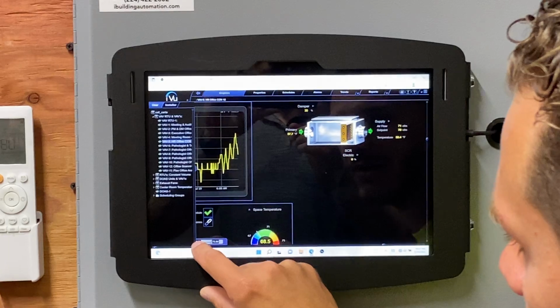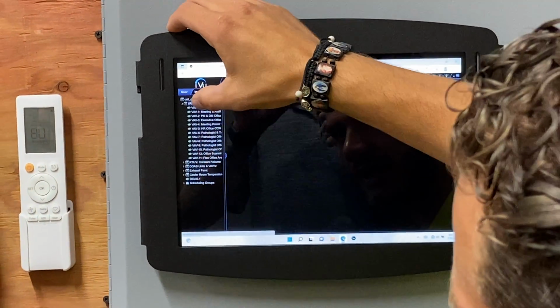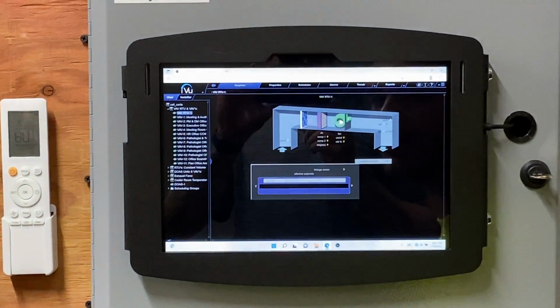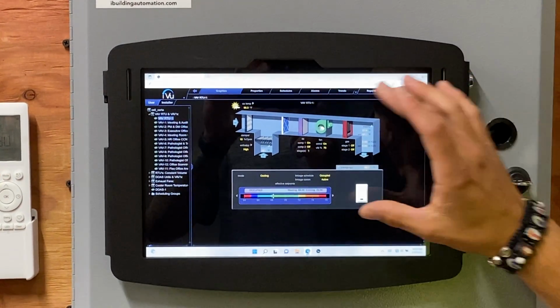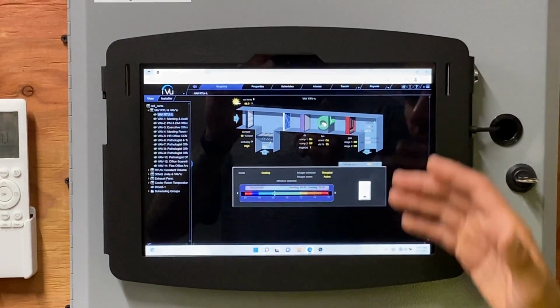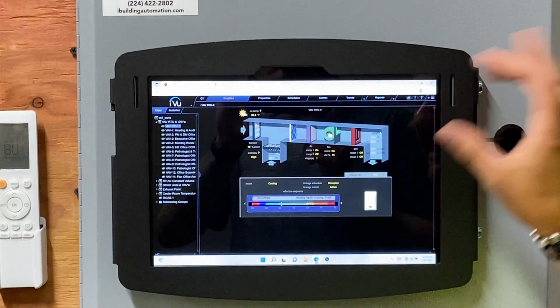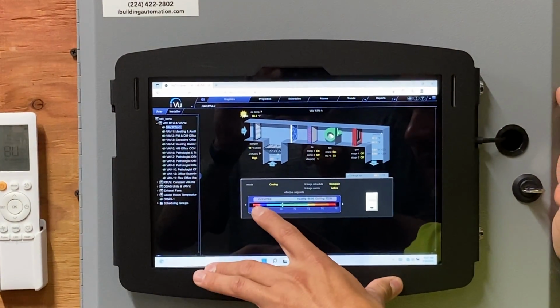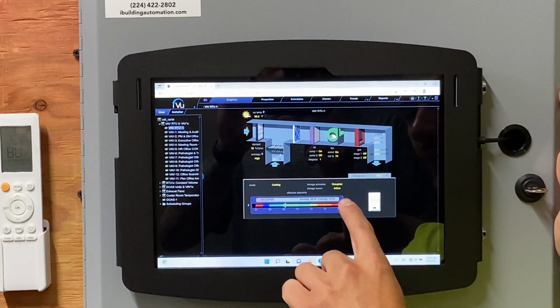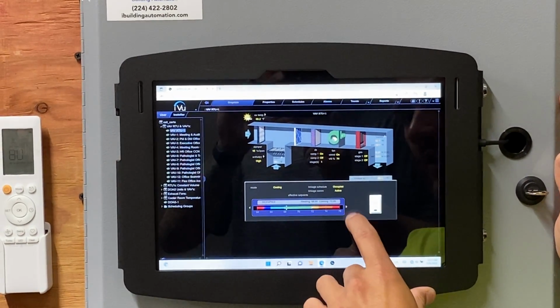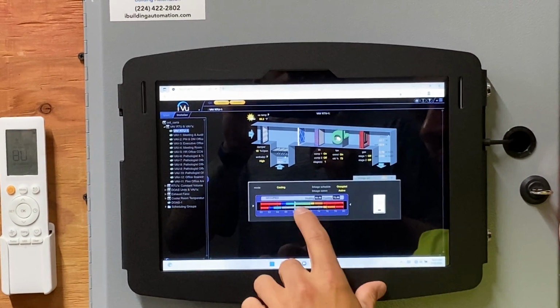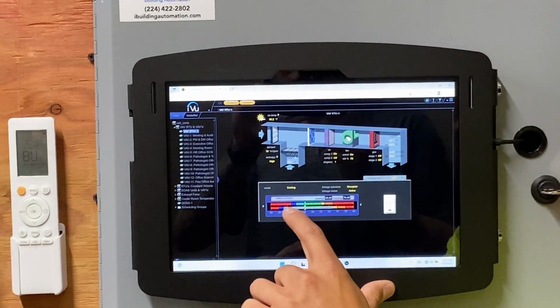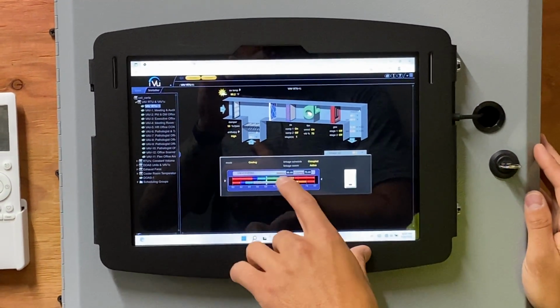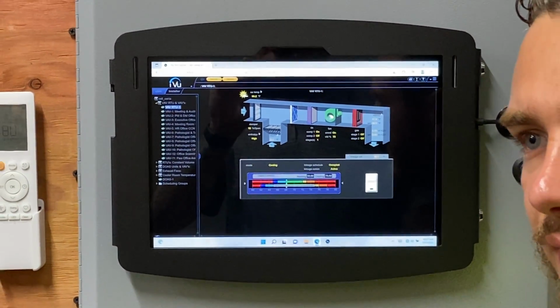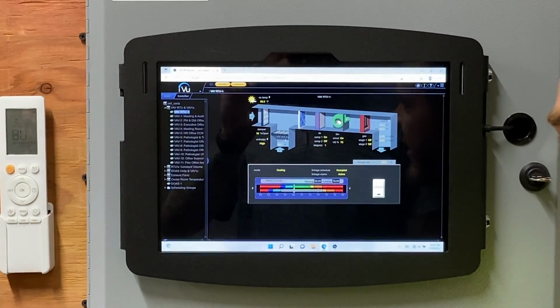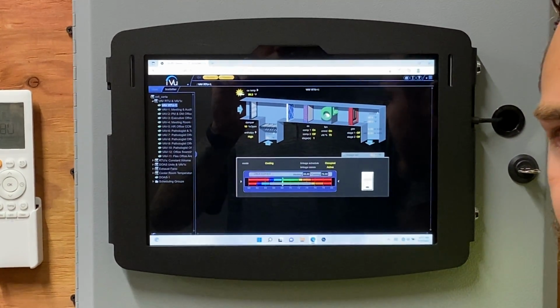So we're going to back out of this page now, and let's say we go to the actual rooftop unit that is controlling these zones. With this graphic, we don't have to do any scrolling left or right, and it's going to show us what's happening for all those zones right now. Again, we have the same thing here, occupied. This one for the rooftop is built a little bit different. You have this arrow here on the side. If you click that, you get that gray bar, and that'll show your unoccupied values. I don't think I went over that. Our unoccupied values are 65 for heating and 75 for cooling. So we'll want to stay in between 65 and 75 during unoccupied periods.